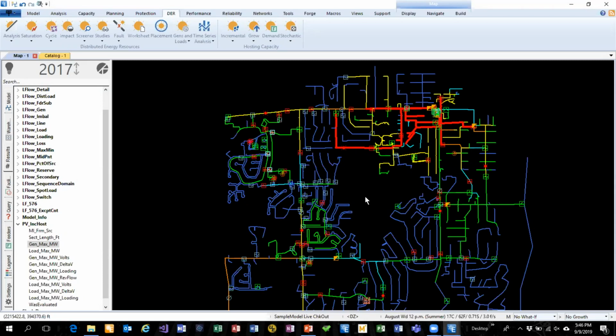The next big step for us on hosting capacity is to account for switching, so it's a marriage of contingency analysis and hosting capacity. That's going to be a big one, because a lot of you have rules in place - it's not so much about the engineering analysis, it's about rules that you have. So we have to capture that. Some of you have systems where you actually turn off the PV system if there's an alternate switching situation, so there's a lot of stuff we'll have to deal with there.